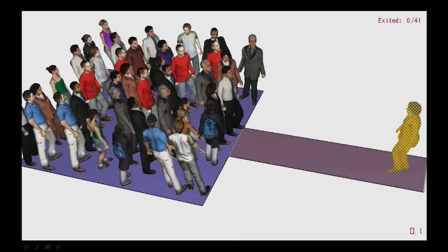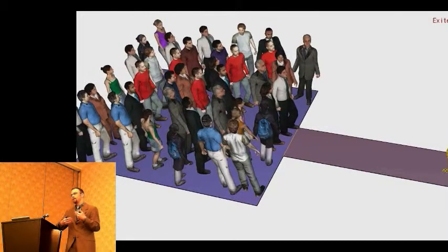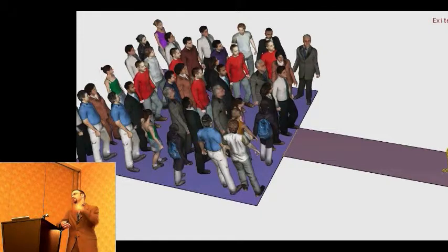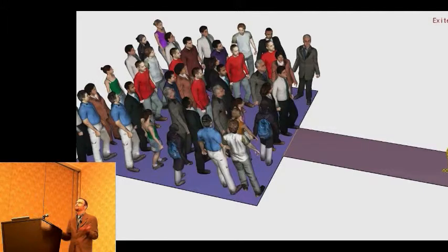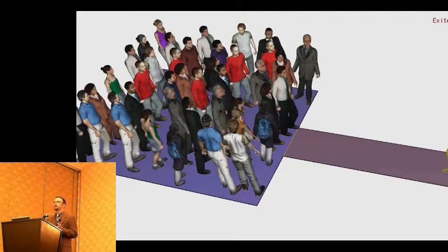Basically, in evacuation mode, the elevators return to the lobby area. To use them for evacuation, the current thinking is that they return to the fire floor, evacuate that entire floor, then sequence other floors — a floor or two above or below the incident floor — and if the local commander desires, finish evacuating the entire building from the top down. We need to determine the order in which floors are cleared and how long it takes to fill an elevator and travel from the ground floor up to any given floor and back. With that basic set of inputs, the elevator model requires you to simply input elevator sizes and travel times, then sequence them and set up a particular case.